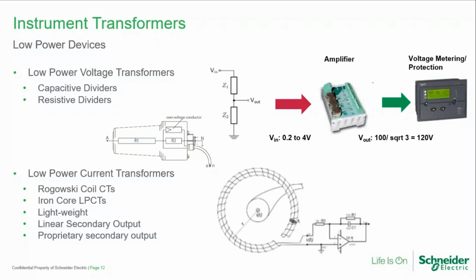Looking at the current transformers, there are some similarities to the low power voltage transformers, but really some of the benefits we get here are lighter weights, smaller footprints when we go to things like Rogowski coil CTs, as well as higher levels of accuracy, or more linear designs of accuracy. And when I say more linear designs of accuracy, I mean that you don't have to worry as much about the ratio of the CT, whether it's 100 to 5, 200 to 5, 500 to 5.